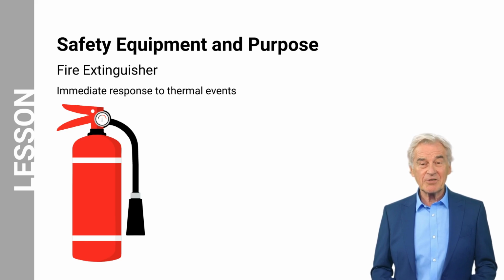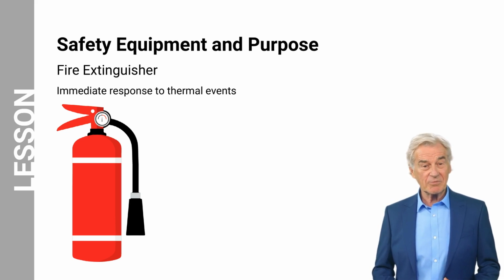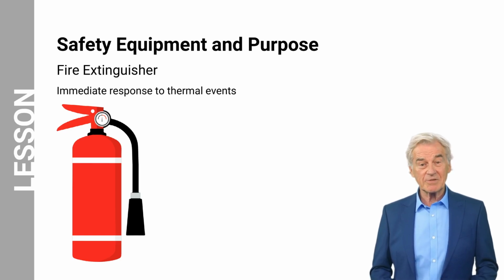Let us look at fire extinguishers. Lithium is a combustible metal, and thermal events involving lithium batteries can be extremely dangerous. Class D fire extinguishers are designed to extinguish fires involving combustible metals but are not always effective on lithium battery fires, which can be difficult to extinguish because they can reignite even after being put out. This is because lithium batteries can contain flammable electrolytes that can be ignited by heat or moisture. If you see a lithium battery fire, evacuate the area immediately and call 911 if in the U.S. Technicians should not engage in lithium battery thermal events beyond their ability.